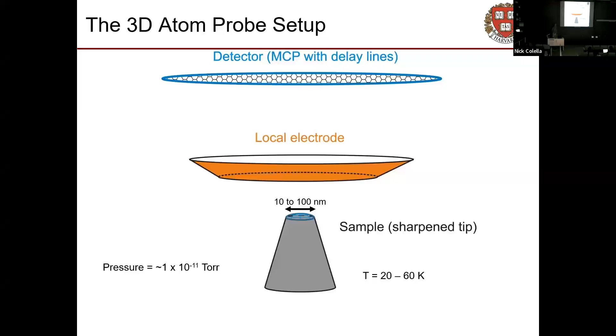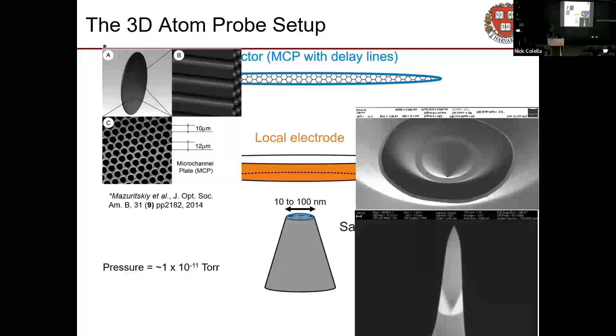And we put it under ultra-high vacuum again, so everything's got to be clean, it's got to be dry, all the same practically applies. And then way up behind the hole in our electrode, we've got a fancy detector called a microchannel plate, which is basically you take a capacitor and drill a bunch of holes in it. Please don't do that.